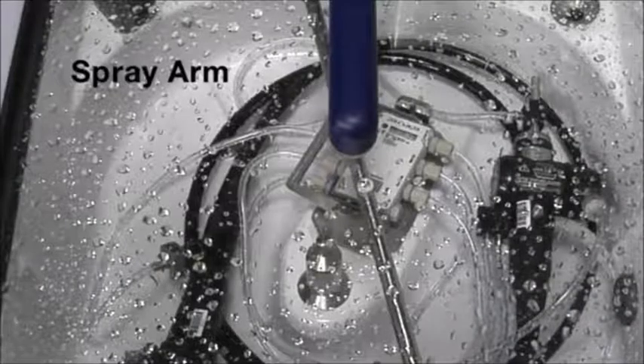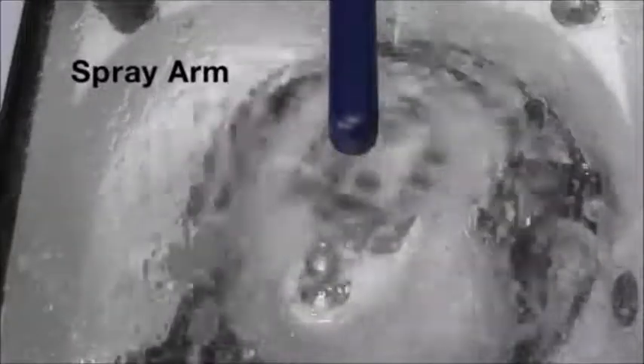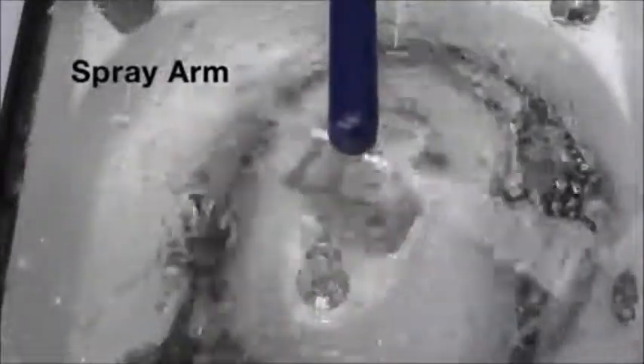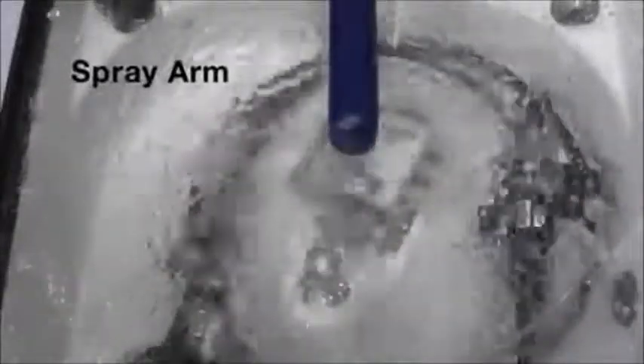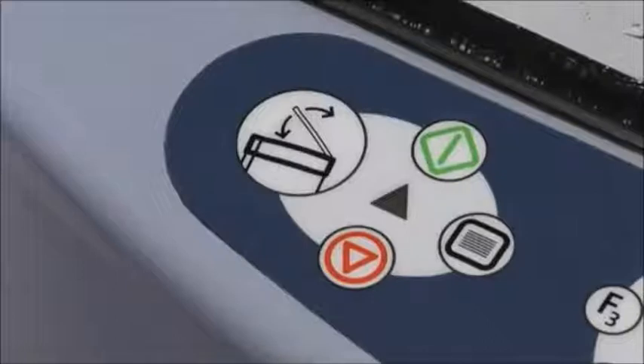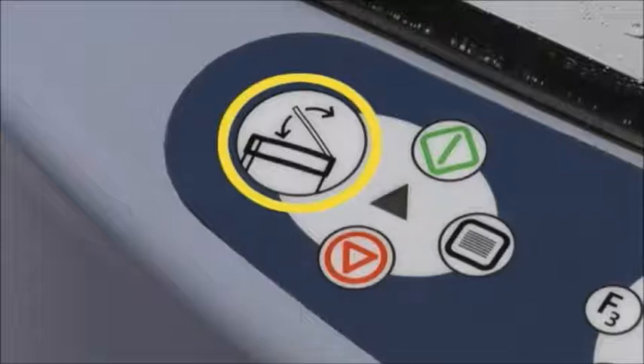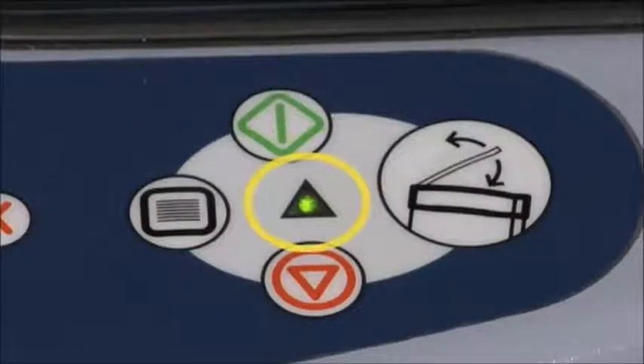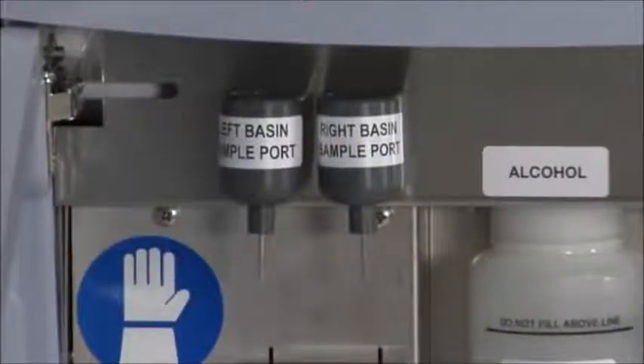The spray arm, located on the basin lid, provides fluid spray for disinfection and rinsing of the exterior surfaces of the endoscope. The use of the spray arm reduces the amount of fluids needed during the reprocessing cycle. Each side is controlled by its own keypad grouping called the basin control buttons. These buttons include the Start button, Cancel button, Menu button, and a button to open or close the lid. An LED will display green if the module is operating normally or red if a system error has occurred. Each side also has its own foot switch for hands-free opening or closing of the lid. Inside the machine are two sample ports, one for each side. The sample port dispenses high-level disinfectant for concentration testing with a test strip at the end of the cycle.